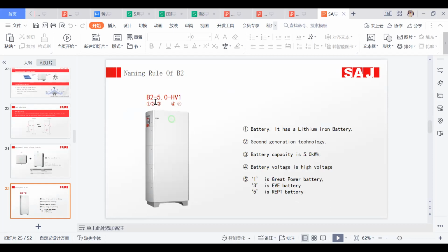First, we could see that for our B2 batteries, the 5.0 means the capacity is 5.0 kilowatt hour, and HV means high voltage. 1 means that the cells are from Great Power battery, different suppliers. 3 means EVE batteries, and 5 means it's REPT batteries. They could not be used together because they use different CAN communication protocols.